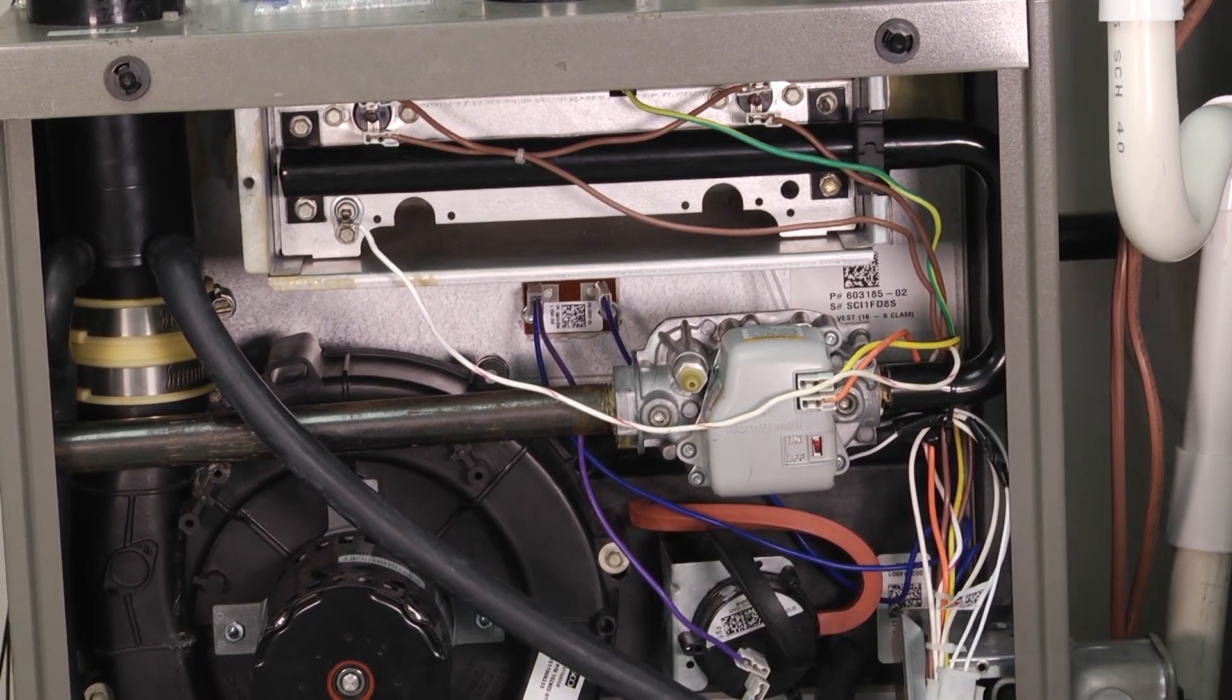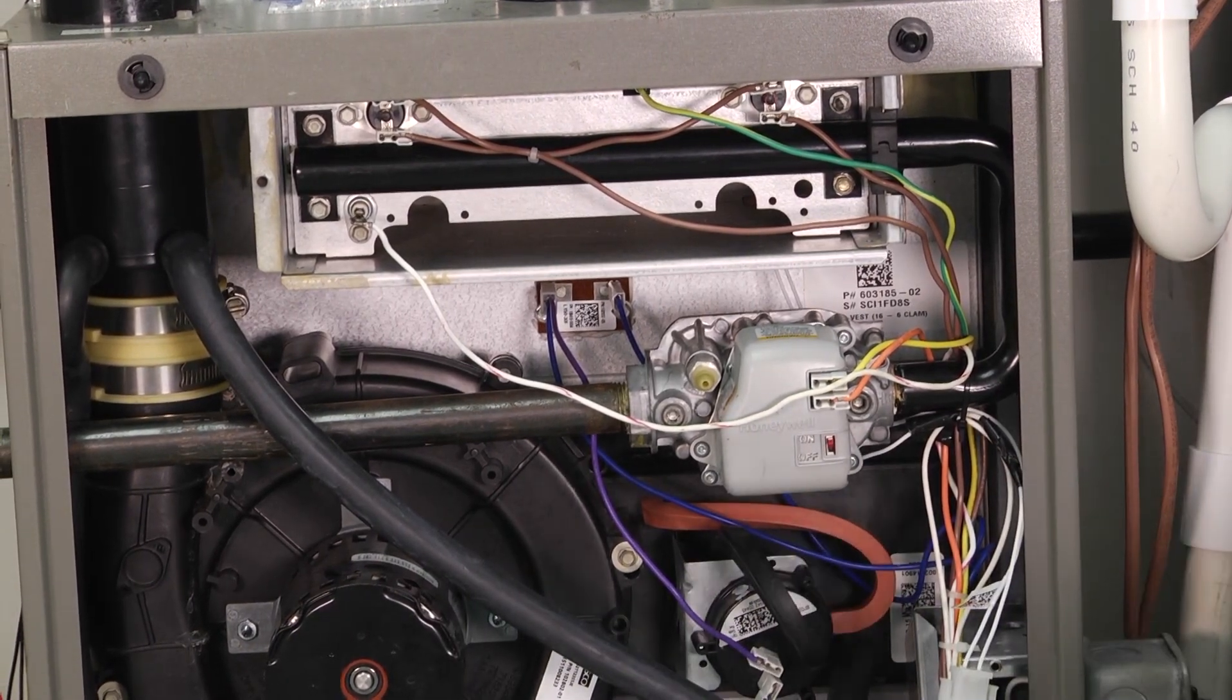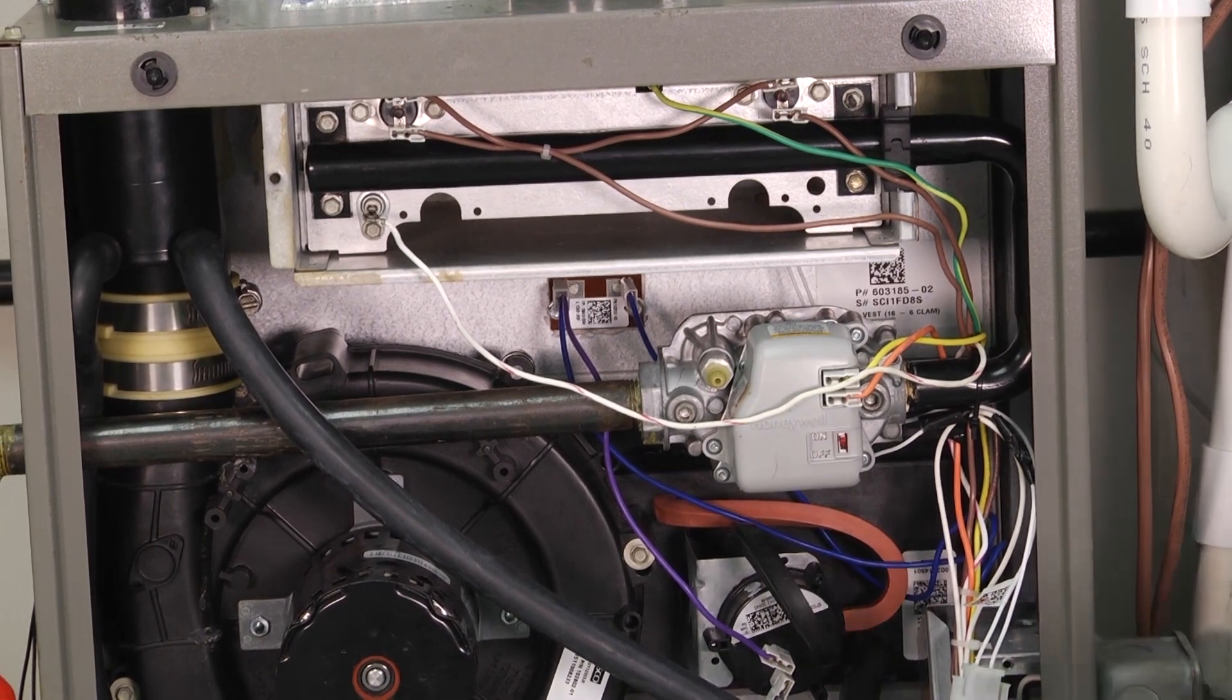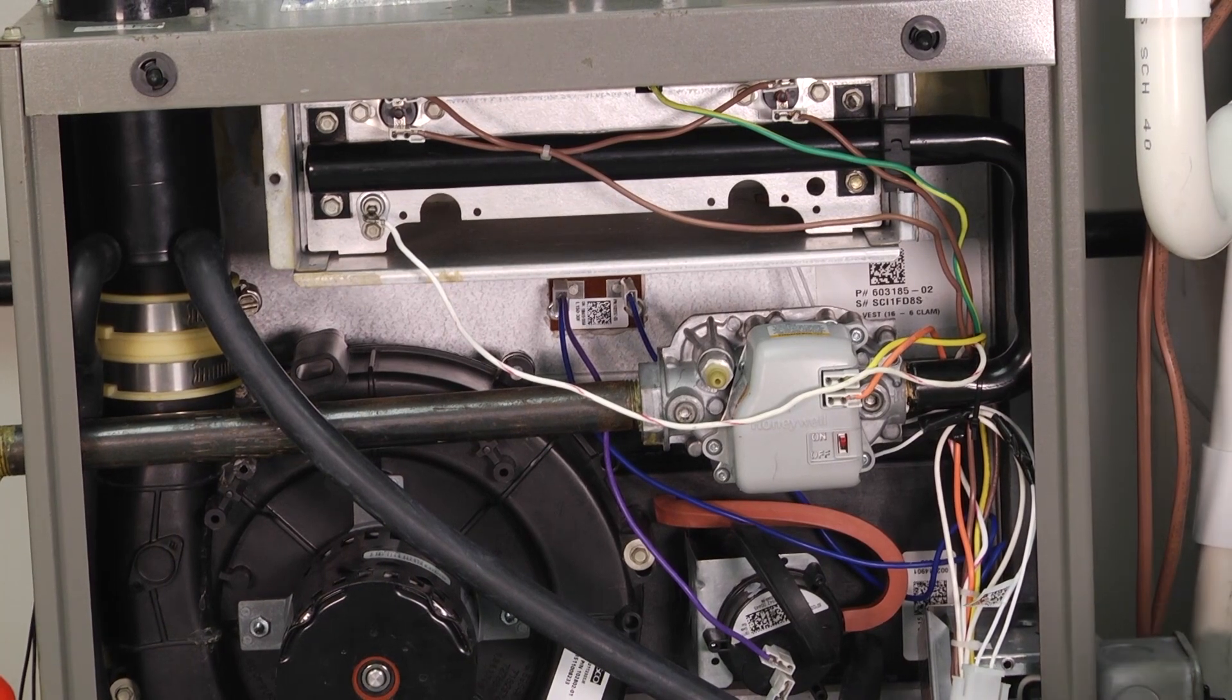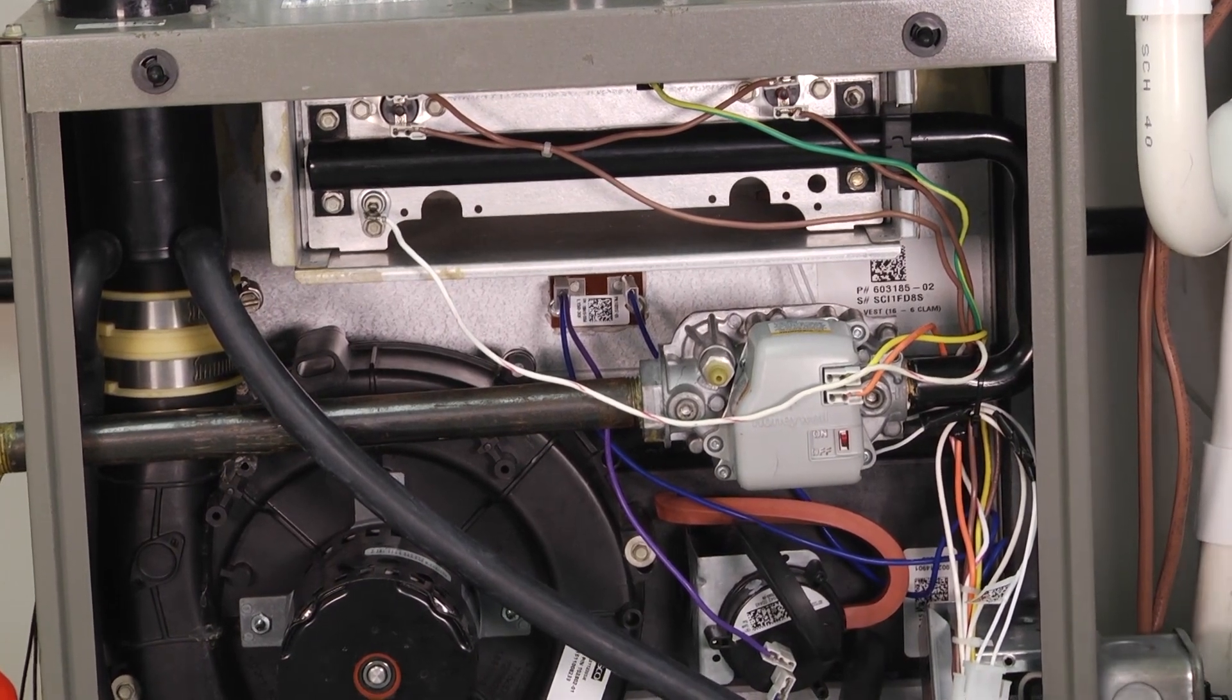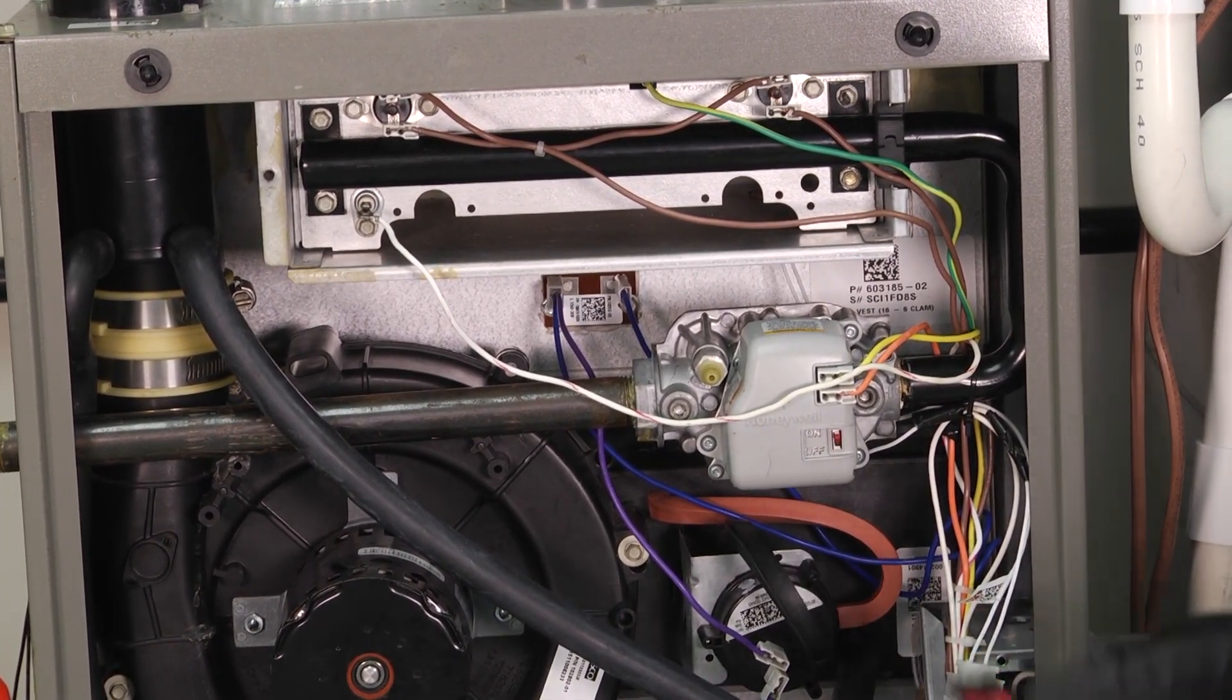Once you do that, you take that information and if it's in the good range, then you tell the homeowner that, hey, your igniter tested at 47 ohms and according to the manufacturer, that's good. No need to worry there.